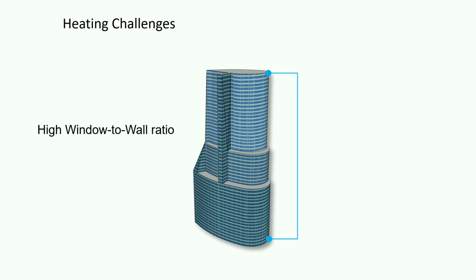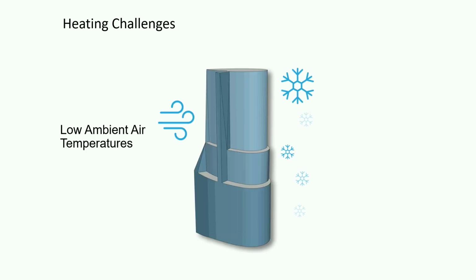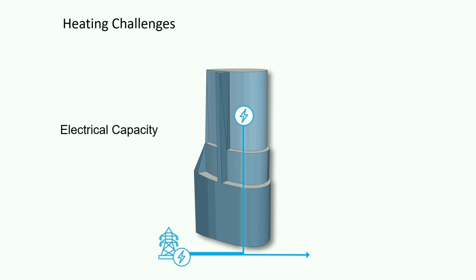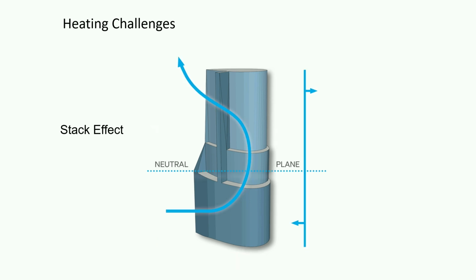Again, window to wall ratio, I mentioned this. Generally, you're getting a lot more windows than walls. So understanding how that impacts your thermal profile and then your comfort within the building, okay? Obviously, we're in New York. This is a heating dominant climate zone, so we need to understand that. What's the comfort going to be like in the building because of that? Your electrical capacity: we're electrifying these buildings. This is all going to change from your traditional systems, right? So we've got more electrical capacity that's required for these buildings. You do get the stack effect. With tall buildings, this is definitely an important thing to consider when you're designing these buildings, okay? Especially in your corridors, elevator shafts, et cetera. You've got to look at all the stack effect, and that really does come into play.